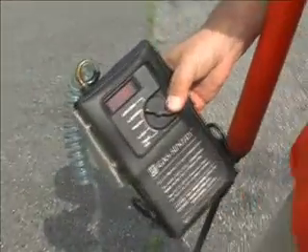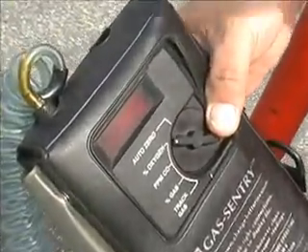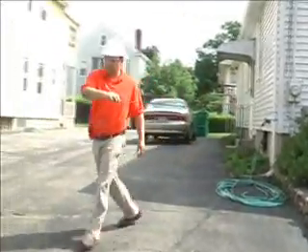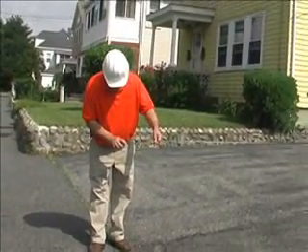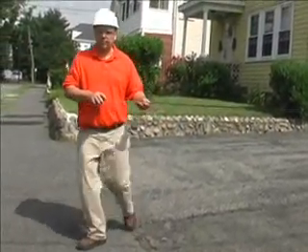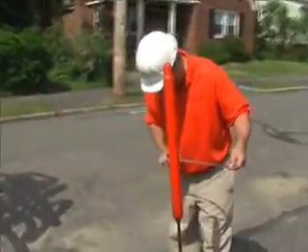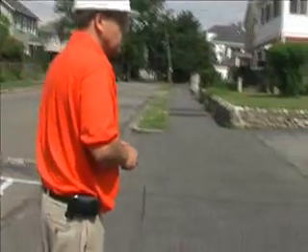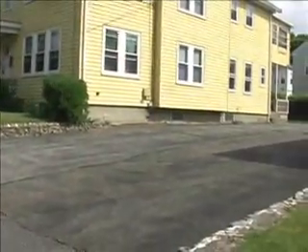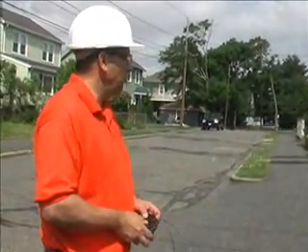We had a 5% gas reading that vented down here with 15 oxygen. So we had 5% gas 23 feet from the house. And street to curb is, I'll round that up, about 30 feet. Continuously paved area up to the structures makes it more of a hazard because in frost conditions it can migrate right underneath this asphalt and get up close to the building.